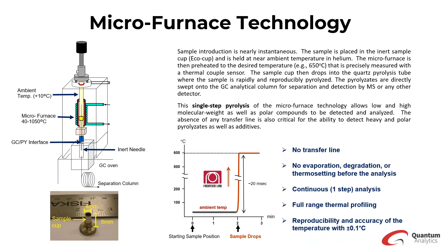The sample cup pictured here only requires microgram amounts of your sample, as is cut, scraped, punctured, or whatever have you from your polymer. And once pyrolysis begins, all of the pyrolysates, or the products of your thermal sampling, are swept right into the inlet to be separated and analyzed by the column detector. The sample cup is only dropped into the furnace when the furnace is heated and ready. So this means there's no degradation, evaporation, or thermosetting before analysis occurs. This is a true pyrolysis reaction, and this furnace reproducibility is plus or minus 0.1 degrees Celsius, and it is precision measured. So that means when you're controlling that furnace temperature remotely, you're actually pretty close to controlling the sample temperature as well.